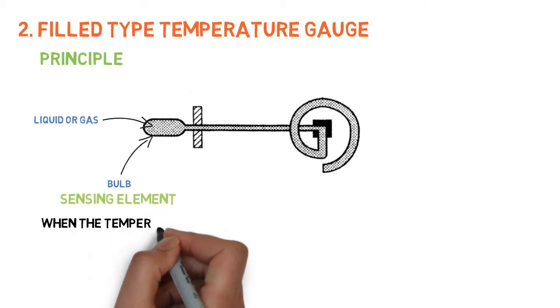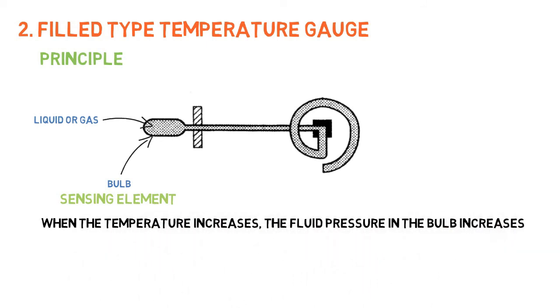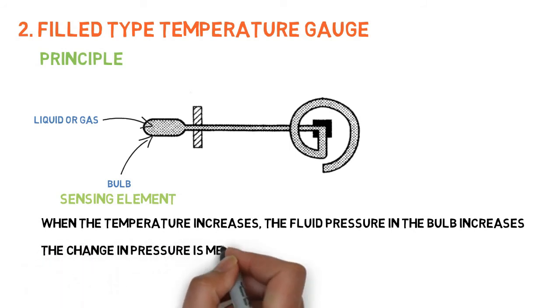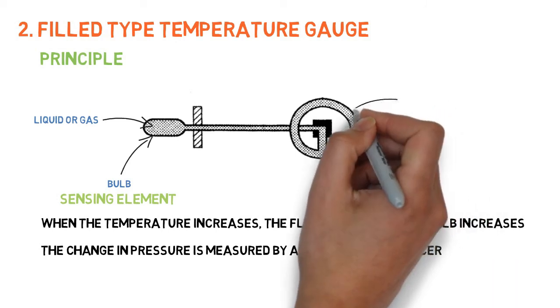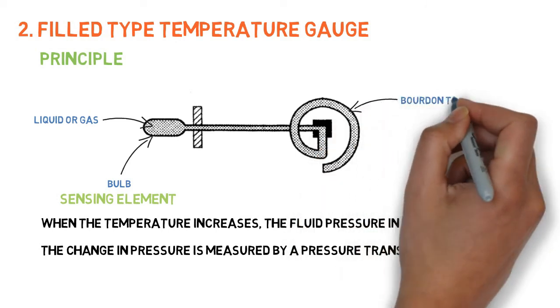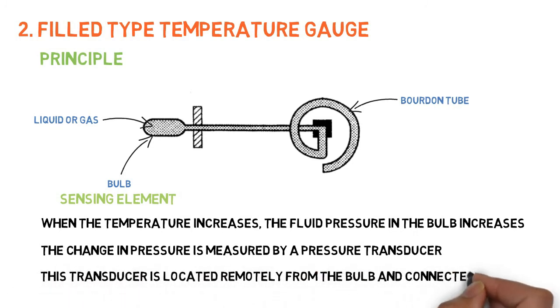When the temperature increases, the fluid pressure in the bulb increases. The change in pressure is measured by a pressure transducer such as a Bourdon tube. This transducer is located remotely from the bulb and connected to it by a capillary tube.